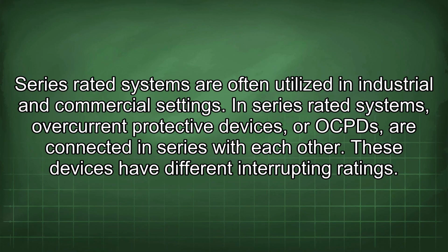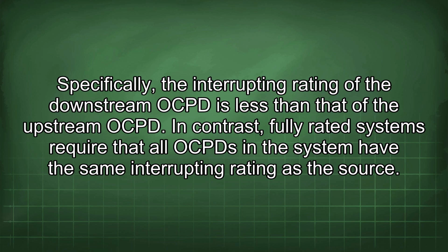Series-rated systems are often utilized in industrial and commercial settings. In series-rated systems, overcurrent protective devices, or OCPDs, are connected in series with each other. These devices have different interrupting ratings. Specifically, the interrupting rating of the downstream OCT is less than that of the upstream OCT. In contrast, fully rated systems require that all OCPDs in the system have the same interrupting rating as the source.